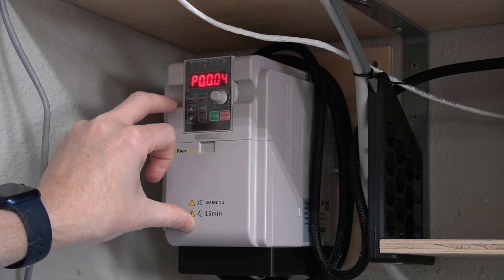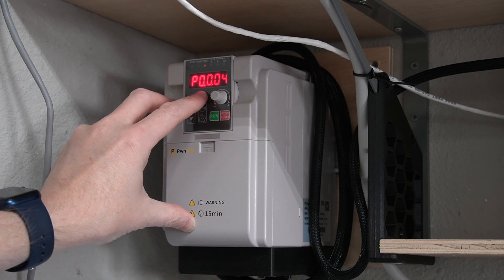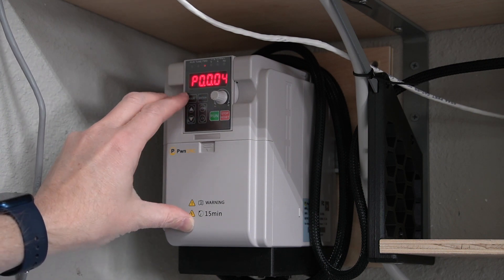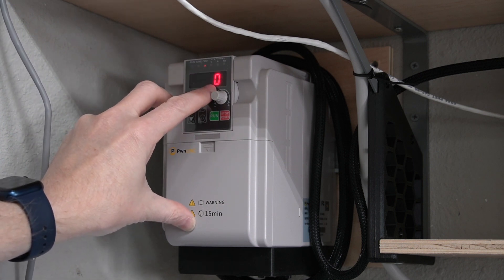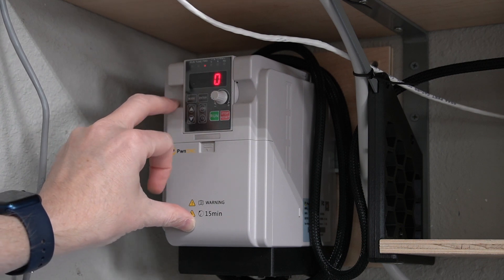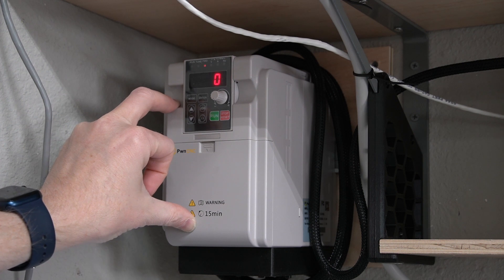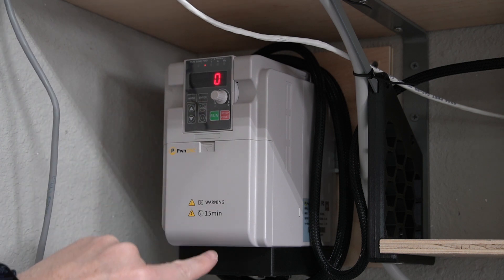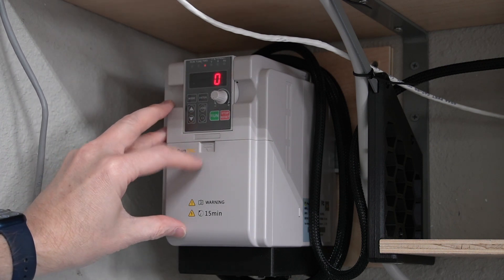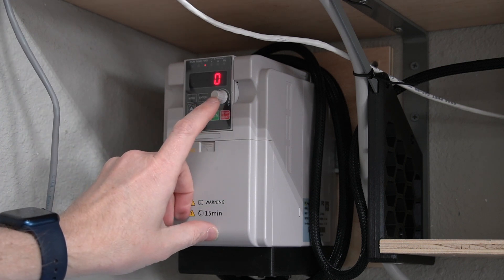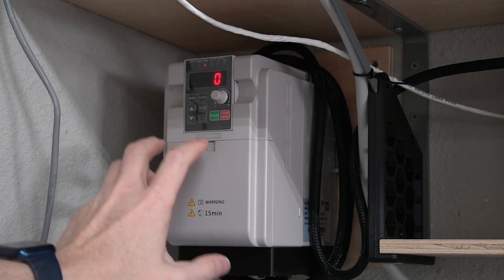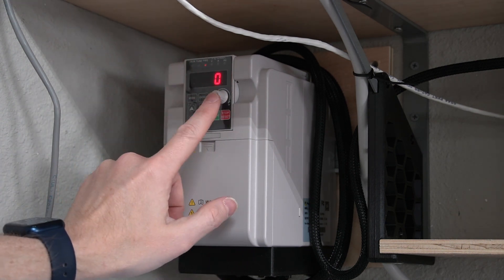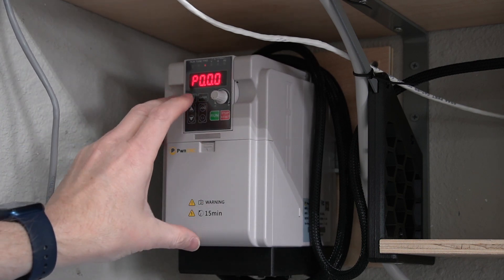We're going to change this to P0.04. Now this is all outlined right here in the manual on page 21. Once you hit set, the up and down arrow in the mode to get to that setting, hit enter. This is the current default setting. We want to change that to a 3. This basically tells the VFD that the PWM signal, or the line that's coming in on VF1, is our frequency controller. So whatever that line says is the frequency. It's going to start ignoring this dial here. Basically disables this dial. So we're going to hit enter and that accepts it.